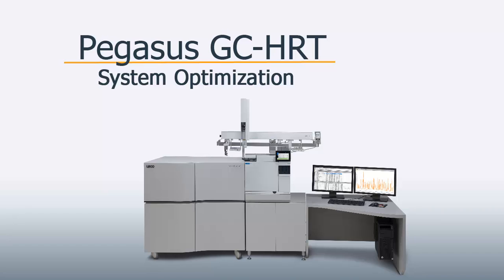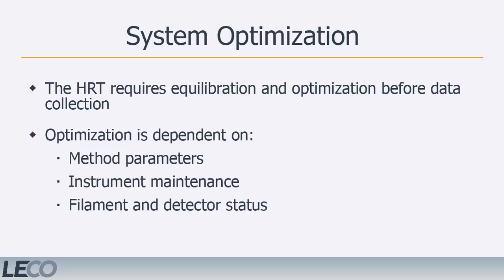This video is a tutorial for system optimization of the Pegasus GC-HRT. Like many instruments, the HRT requires an equilibration and optimization sequence prior to sample collection. The degree to which the instrument must be optimized is dependent on several factors, including the method of analysis, the amount of instrument maintenance performed, the changes in the mass spec parameters, and the status of the filament and detector.